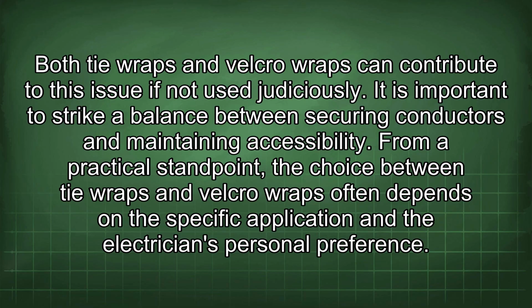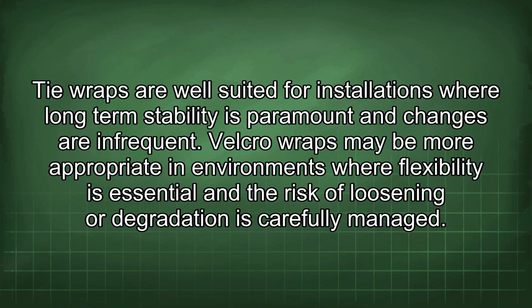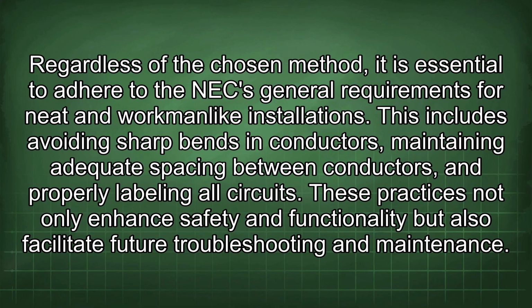From a practical standpoint, the choice between tie wraps and Velcro wraps often depends on the specific application and the electrician's personal preference. Tie wraps are well suited for installations where long-term stability is paramount and changes are infrequent. Velcro wraps may be more appropriate in environments where flexibility is essential and the risk of loosening or degradation is carefully managed. Regardless of the chosen method, it is essential to adhere to the NEC general requirements for neat and workmanlike installations. This includes avoiding sharp bends in conductors, maintaining adequate spacing between conductors, and properly labeling all circuits. These practices not only enhance safety and functionality, but also facilitate future troubleshooting and maintenance.